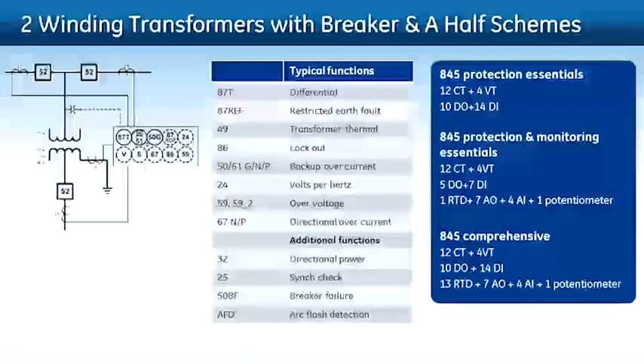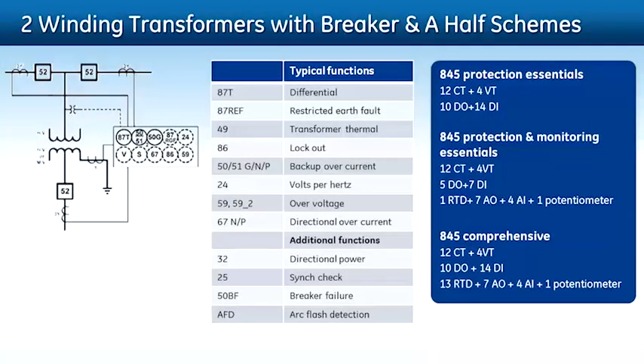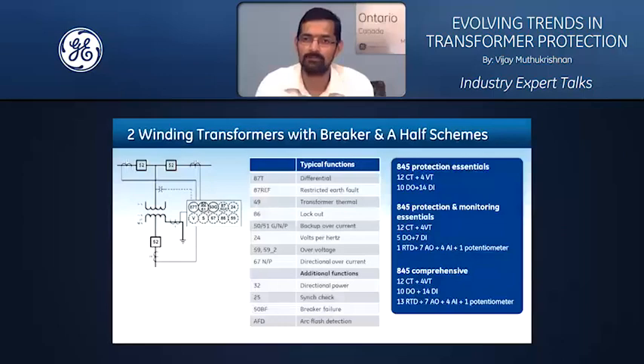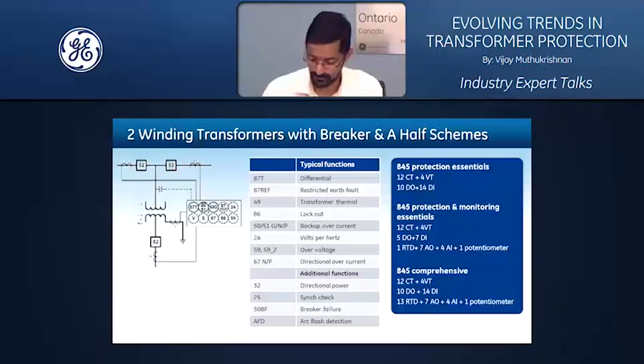Then the other type of application that comes is the breaker and a half scheme, for two-winding transformers. In this case, essentially you have to treat it as a three-winding transformer application in case of an 845, and you pick an order code option that allows you a three-winding application, but you are applying it for a two-winding with breaker and a half scheme, and you can do three-breaker control as well within the same device. That's how you can build protection and comprehensive monitoring and diagnostics for a two-winding transformer with breaker and a half application.